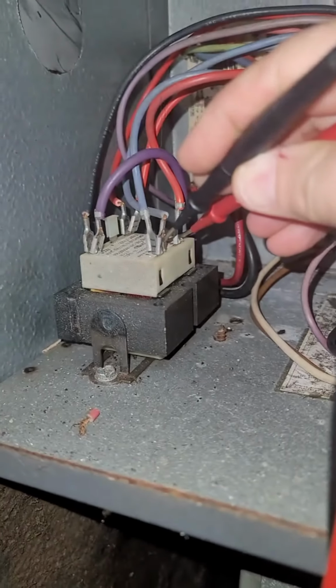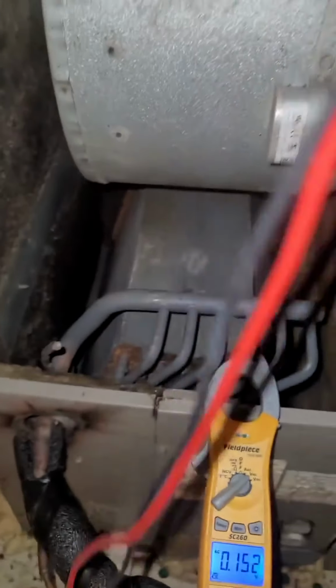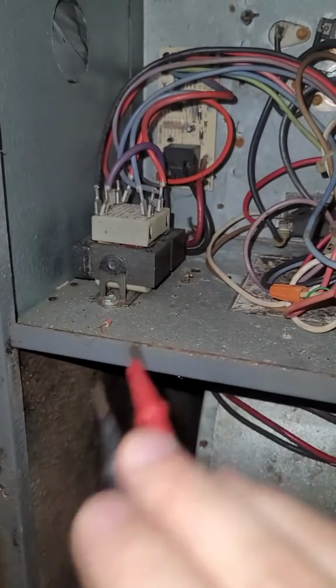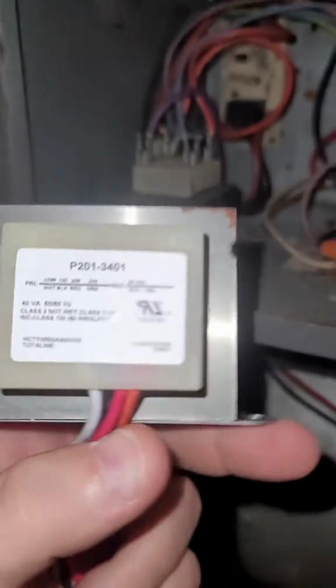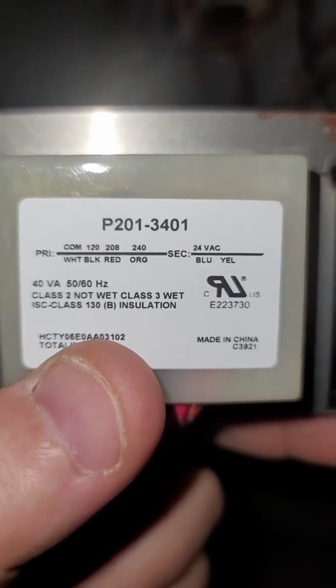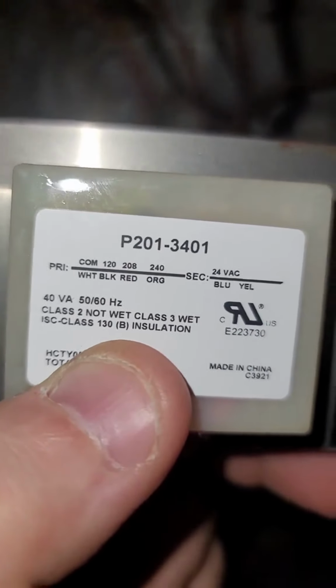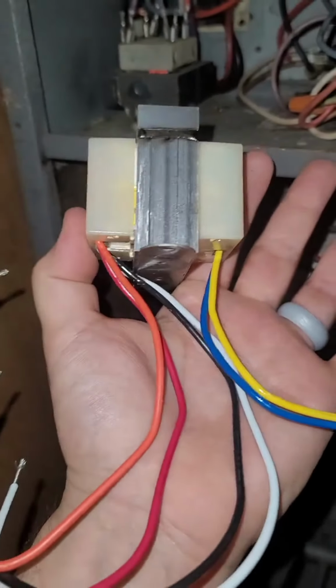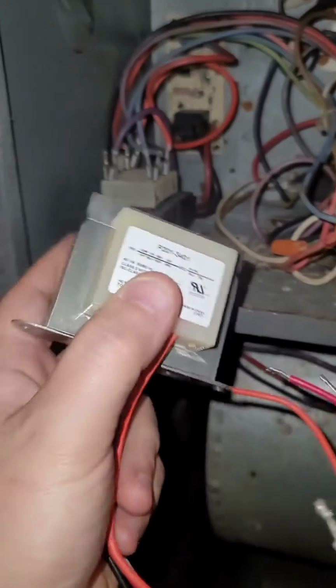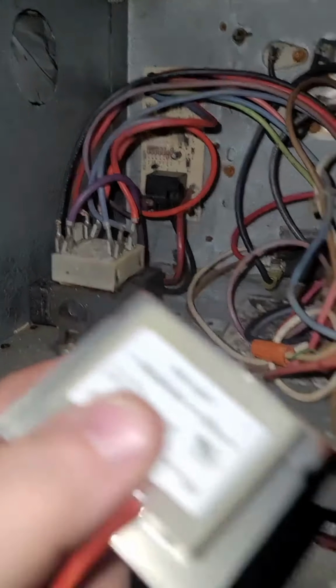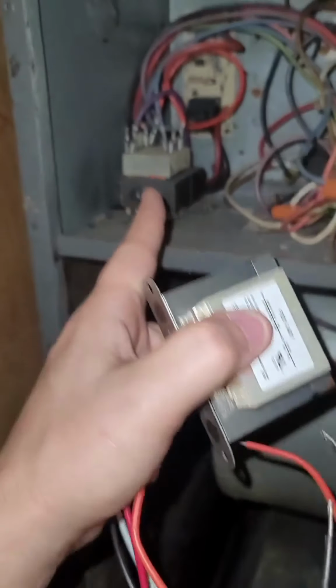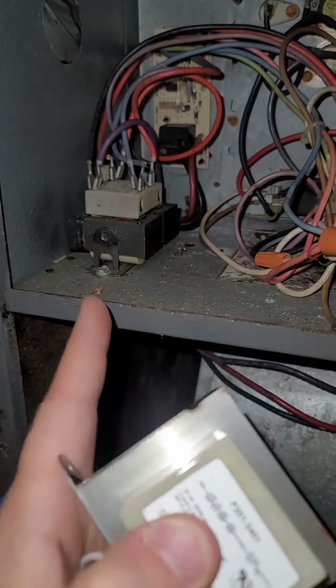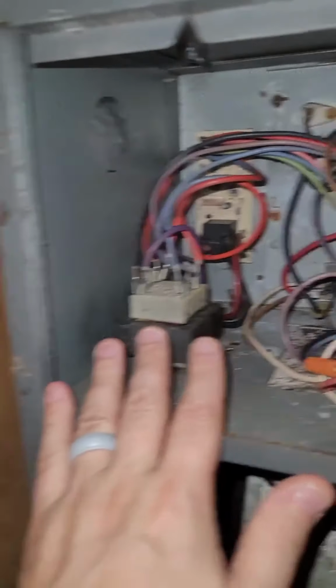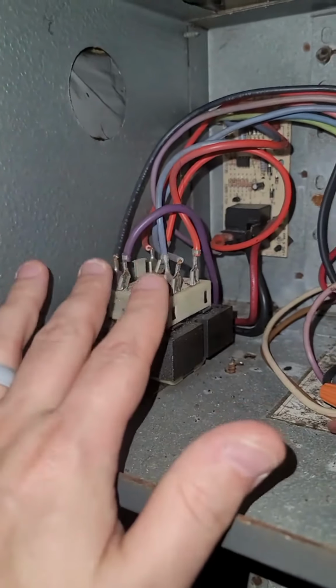Now, these two prongs on this transformer that you're seeing me touch is low voltage. You should actually see 28 volts right there. 28 volts. It wasn't there, so I know it was bad. If you look at this, you see the white is common, 240 is orange. If you had 208, you'd use the white and red. If you had a gas furnace, you'd probably use white and black. That's 110 volts. The blue and the yellow on this transformer is your 24. So you got high voltage coming into the transformer and low voltage coming out. So you have white and orange for the 240 and the blue and yellow for the 24 volts.